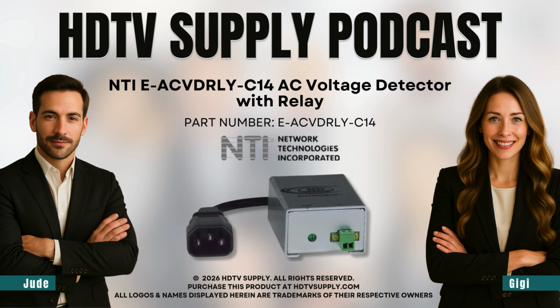And its job is simple. It just tells the system alarm or normal. That's it. It's a very simple, very reliable messenger connected by a basic two-wire cable. And I noticed the detection range is huge, 50 to 250 VAC. So you can use it pretty much anywhere in the world. You can, but the really interesting part isn't just what it detects, it's how it communicates that state without errors. That's where the internal relay comes in. That relay is the whole game. It's a simple open or closed contact switch, but the genius is in the engineering, specifically the trip points.